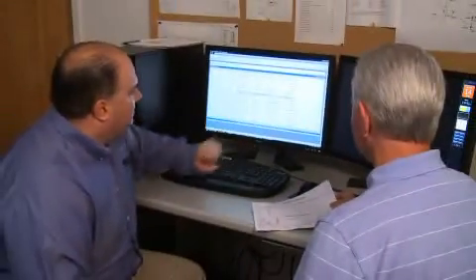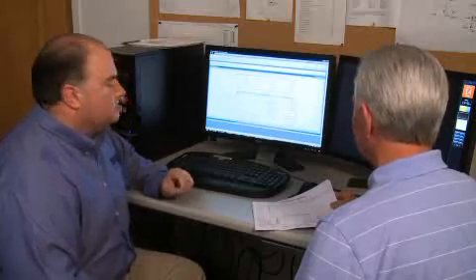What is the Distribution Fault Anticipator and how are you using it? The DFA is a device that we've installed in our substations using bus CTs and PTs to capture currents and voltages and generate capture files when things happen on our system that we want to know about. The DFA automatically recognizes normal system events and separates them from the other events — the faults, the switched capacitors.